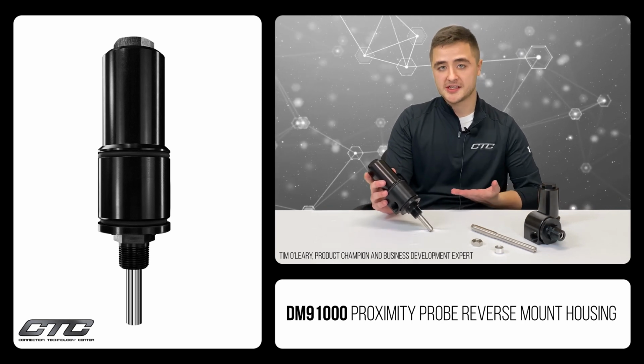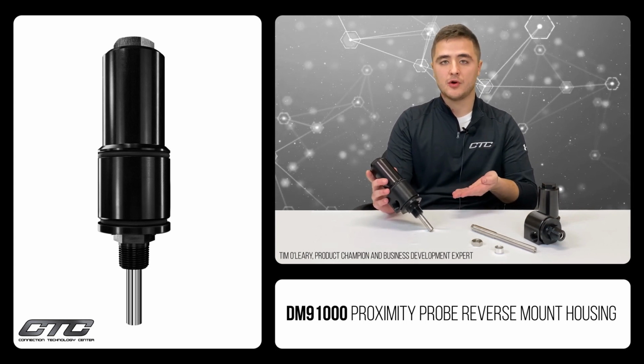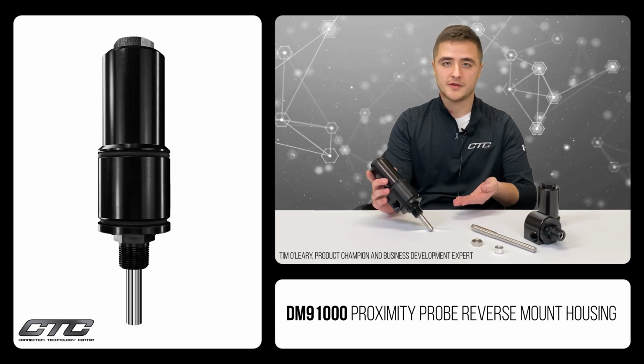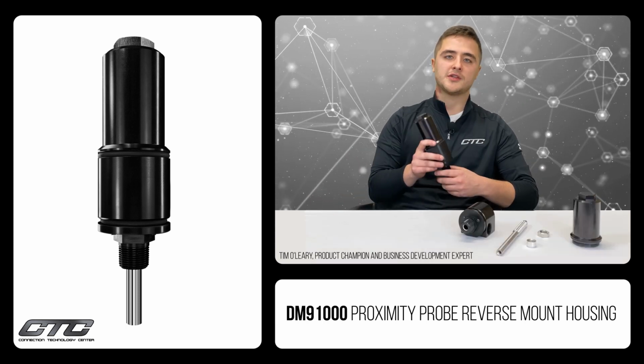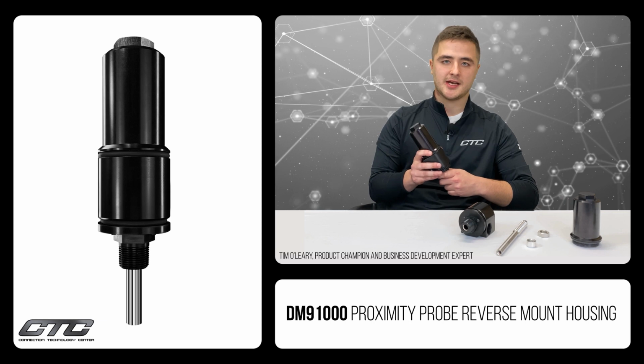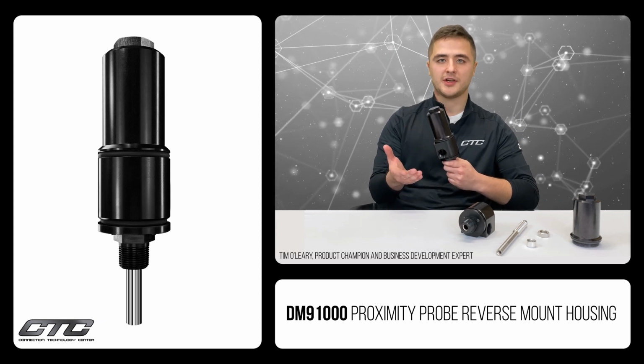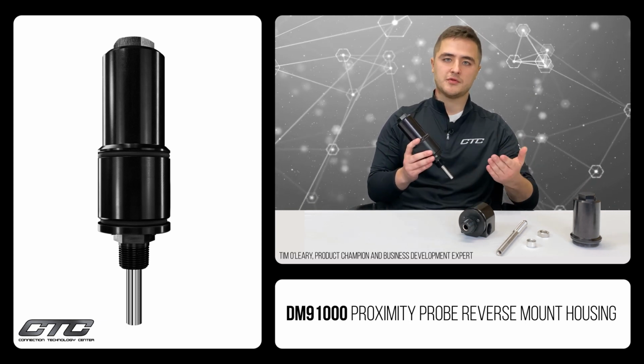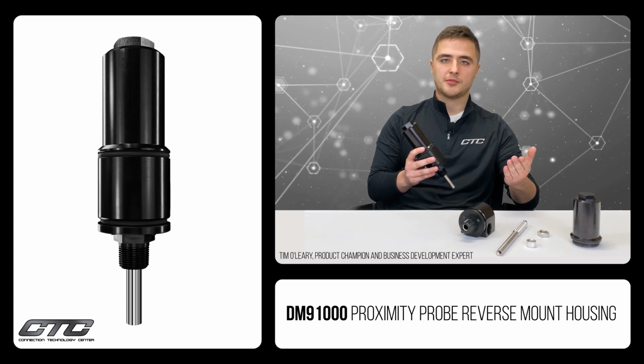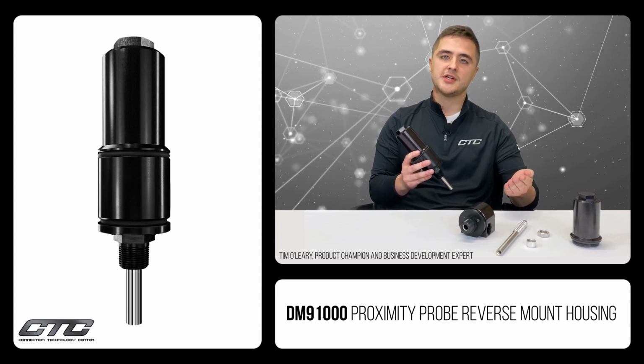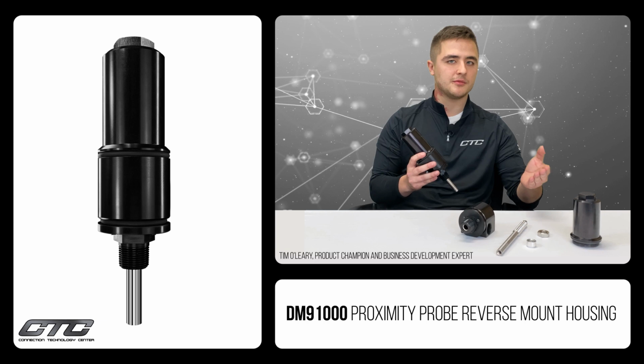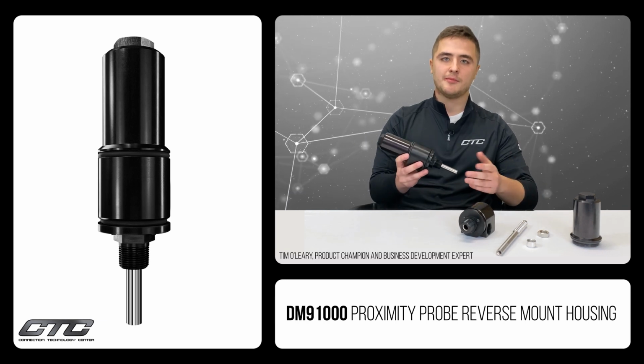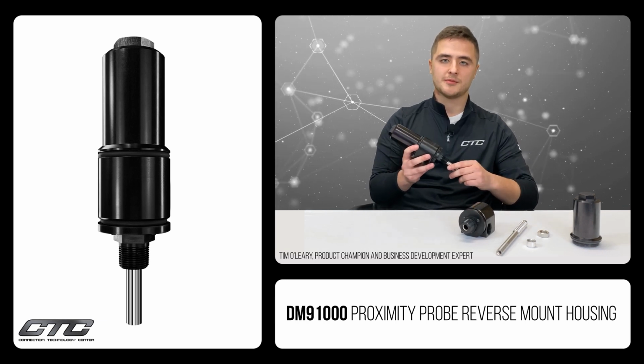This housing is designed to protect your proximity probe assembly in the harshest of industrial environments, while still offering easy access to your probe and extension cable connectors, as well as give you the ability to adjust your proximity probe gap while the machine is running, without shutting down the machine or wasting time by removing your probe system entirely.